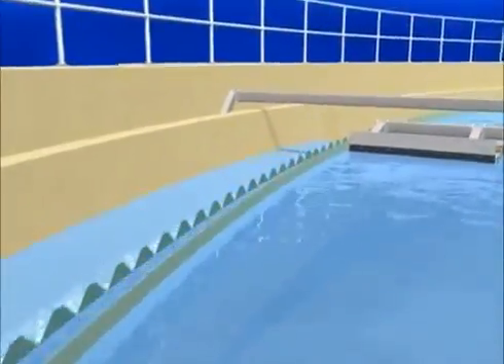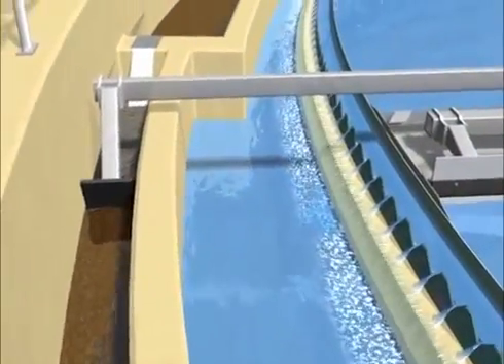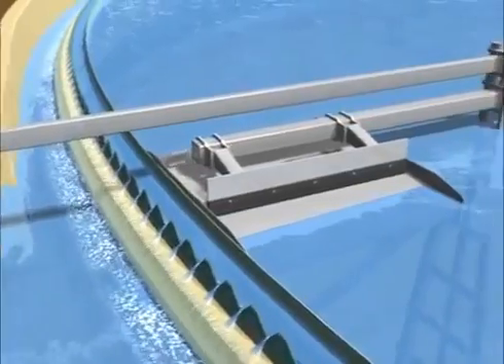Entering flow velocity is further dissipated as it hits an inlet target baffle. The flow is confined by a skirt baffle hanging below the influent-effluent channel. This allows for a downward entrance into the clarifier. As the mixed liquor flows toward the center and solids separate out, the clear water flows up and the sludge flows down. This acts similar to an upflow clarifier as found in water treatment and is highly efficient. The clarified water flows over the weir and into the effluent channel. Skimming is done in the influent channel and main basin.